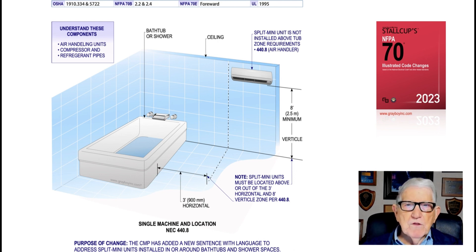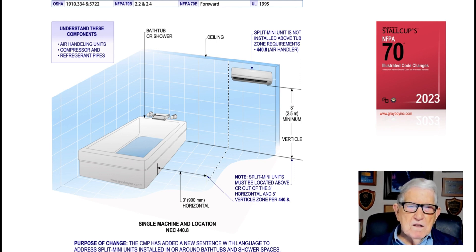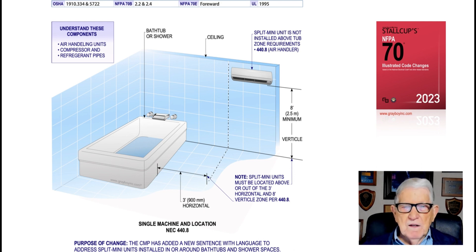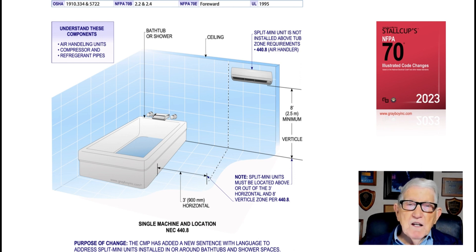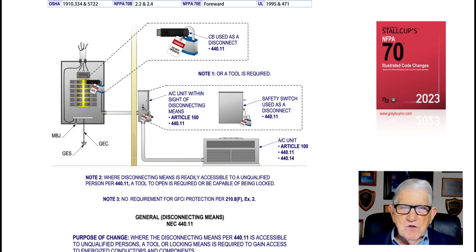Understanding these components, we're looking at air handling units, compressors, and refrigeration pipes that make up this unit, and these can be set anywhere within the dwelling. The note says that split mini units must be located above or out of the three-foot horizontal and eight-foot vertical zone rule. That's what this illustration is illustrating — where you can locate and install these split mini units in a bathroom area.